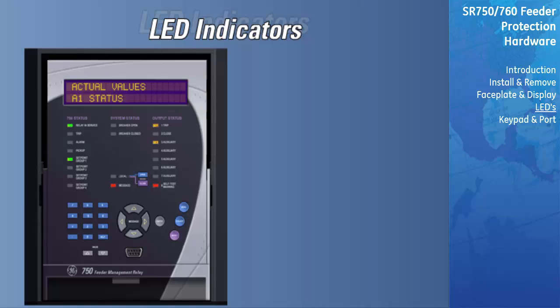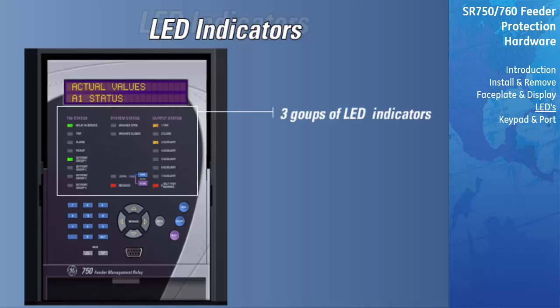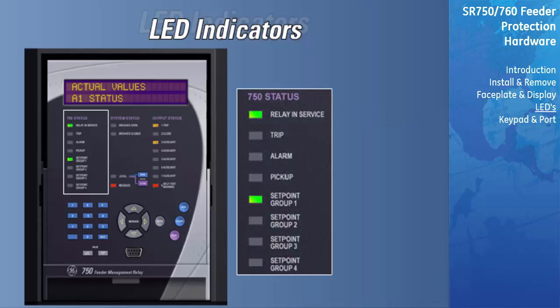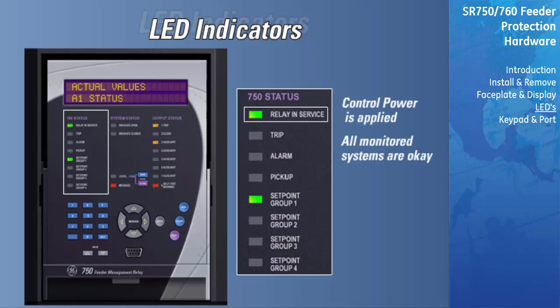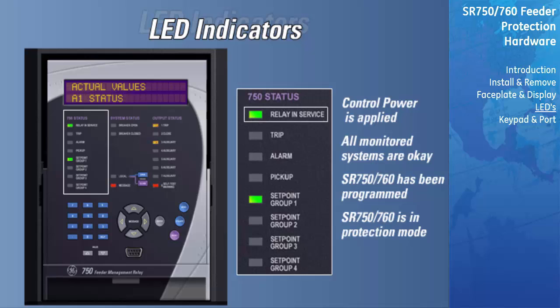There are 3 groups of LED indicators on the faceplate that indicate the status of the relay, system, and output relays. The meaning of these indicators is as follows. First, let's look at the status LED indicators. The Relay in Service LED indicates that control power is applied and all monitored input, output, and internal systems are OK, and the relay has been programmed and is in protection mode, not simulation mode.